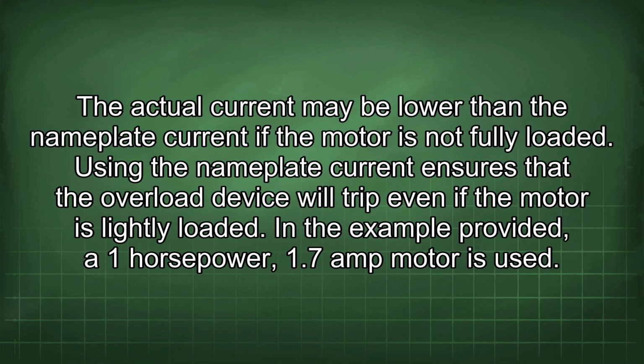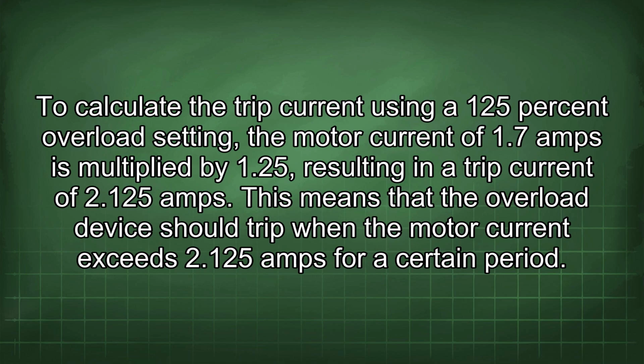In the example provided, a 1 horsepower, 1.7 amp motor is used. To calculate the trip current using a 125% overload setting, the motor current of 1.7 amps is multiplied by 1.25, resulting in a trip current of 2.125 amps. This means that the overload device should trip when the motor current exceeds 2.125 amps for a certain period.